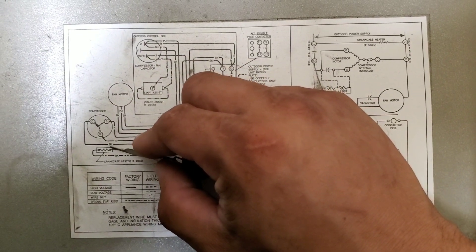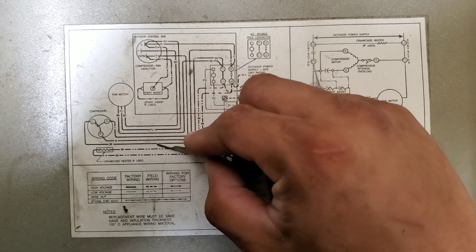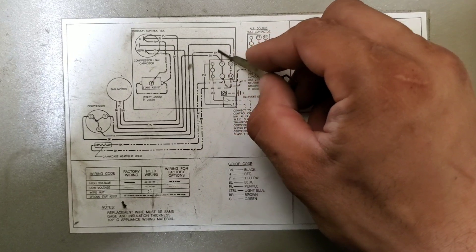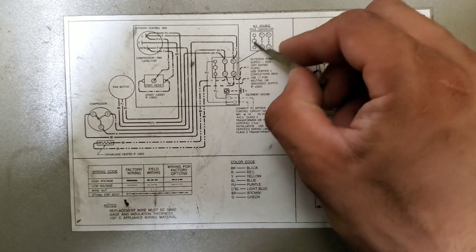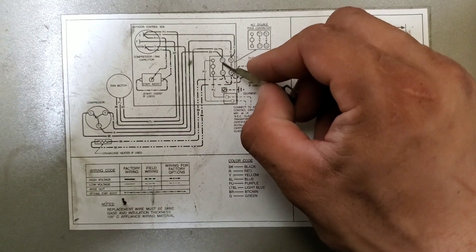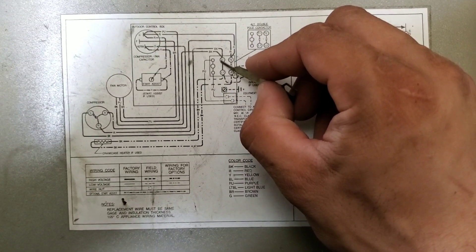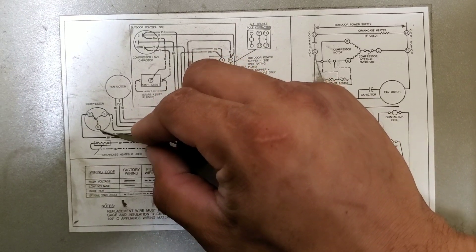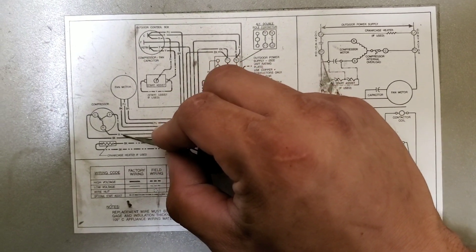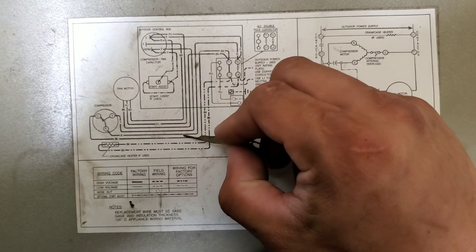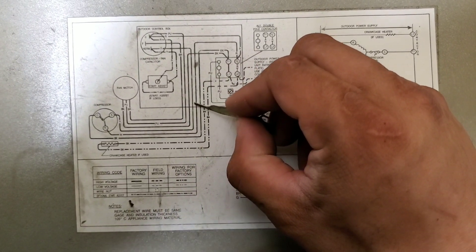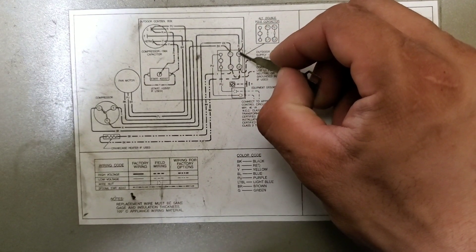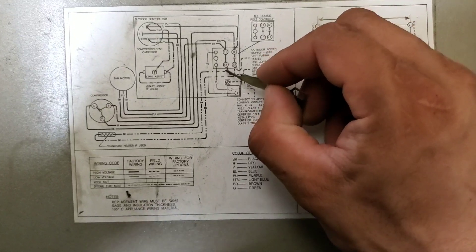If we follow the common, it's labeled black and you'll follow it all the way through. It'll run up and tie into your contactor onto the T1 side. Now we look at our run, the wire is labeled R red, and it feeds all the way through and ties into the T2 terminal of your contactor.